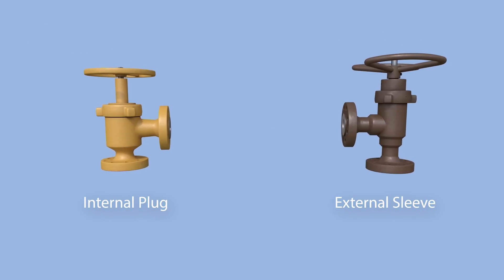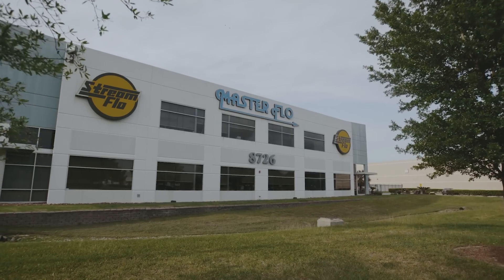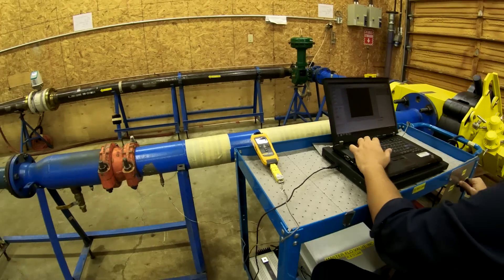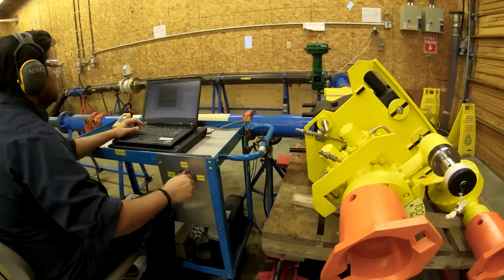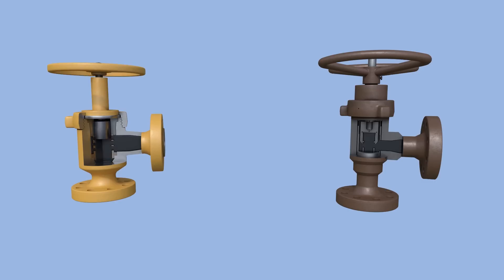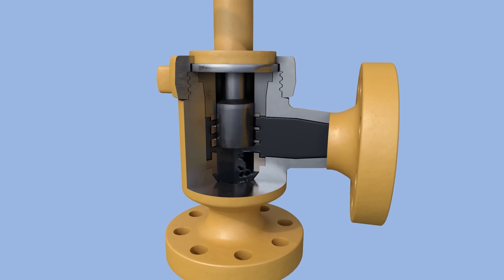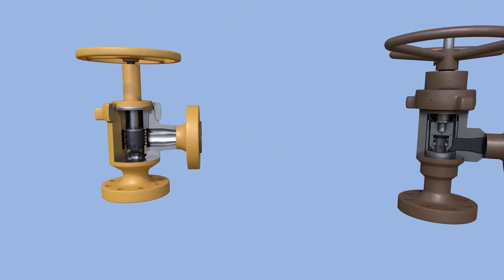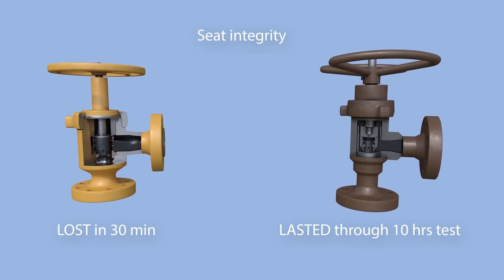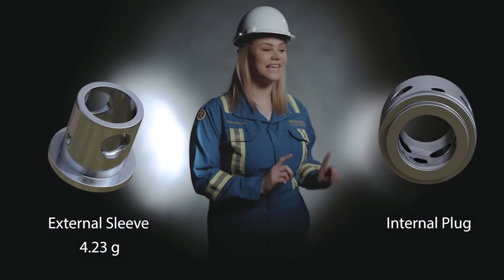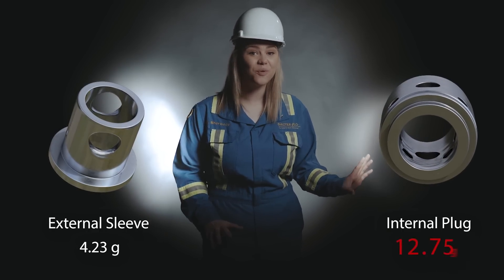MasterFlow tested the effects of erosion at their state-of-the-art testing facility by placing two valves in series, subjecting both to identical sand and flow rate conditions. As the fluid began to move towards the vena contracta — where the diameter of the stream is smallest — the fluid in the internal plug design accelerated in the cage port and directly impinged onto the exposed internal plug, resulting in extensive material loss. The seat integrity of the internal plug was lost within 30 minutes. The external sleeve's seat feature lasted throughout the 10-hour test, with material loss of only 4.23 grams. In stark contrast, the internal plug design lost an astounding 12.75 grams — more than three times the material.